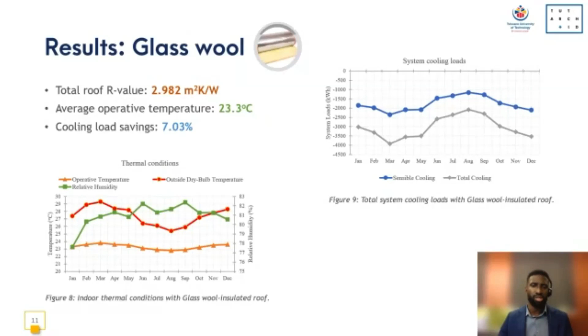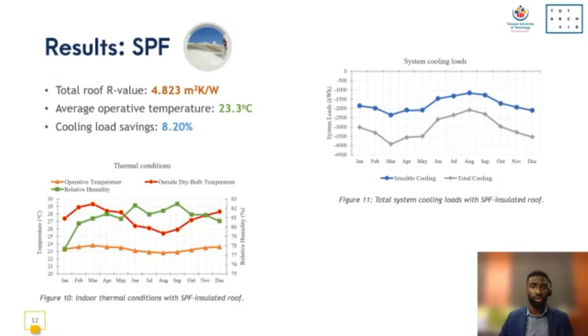Spray polyurethane foam was the final roof insulation material that was tested. This showed the highest R value at 4.823 meters square Kelvin per watt at a similar average operative temperature of 23.3 degrees Celsius. The cooling load savings that was observed was the highest among all 3 at 8.2%.